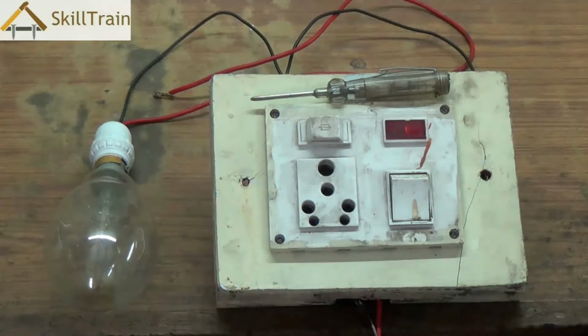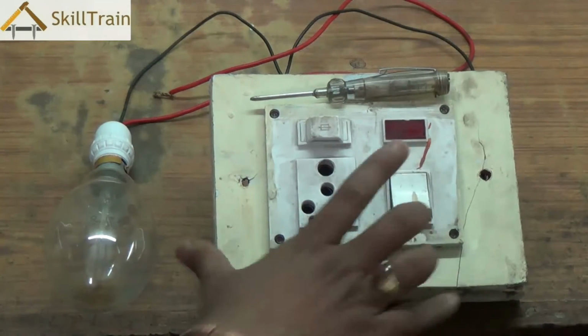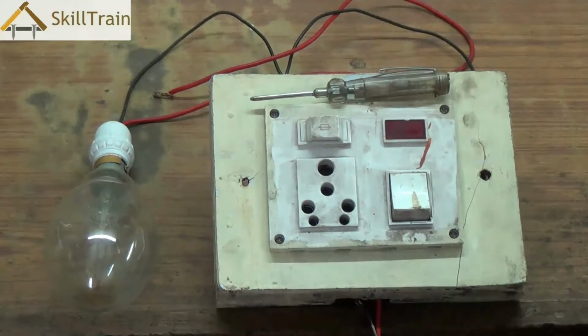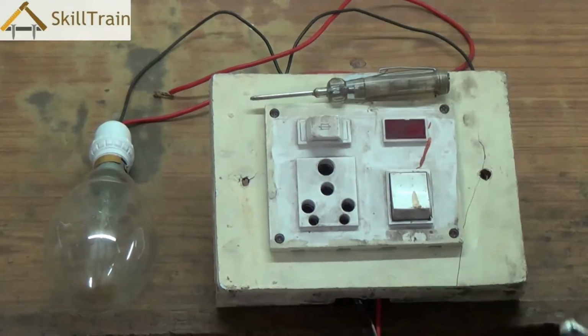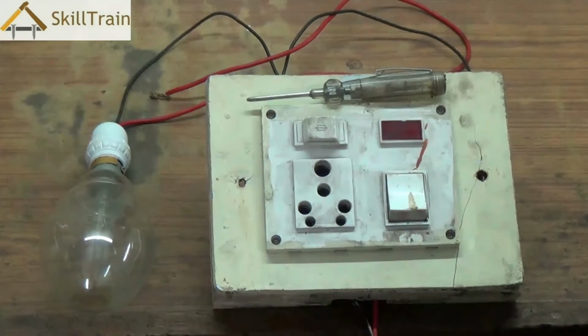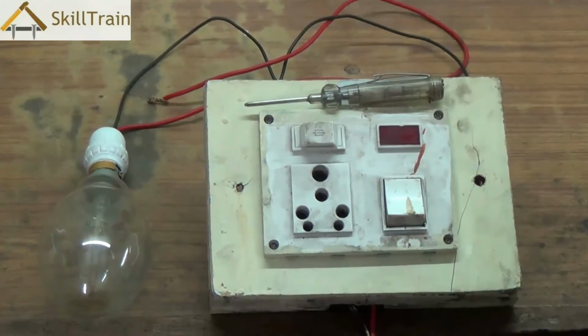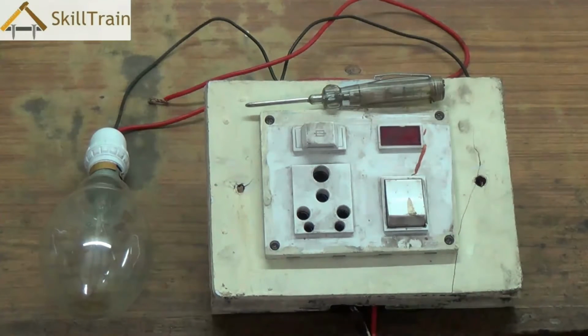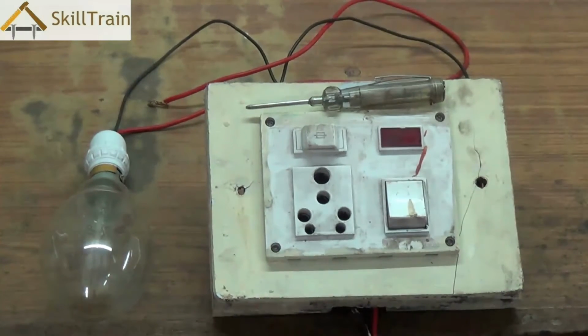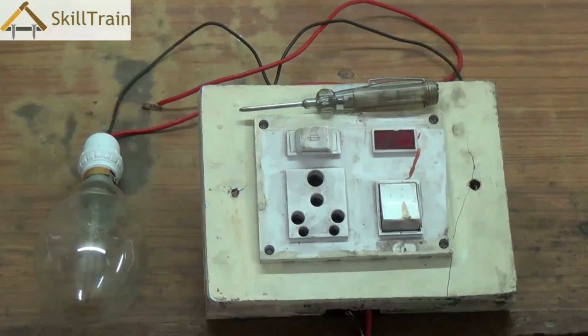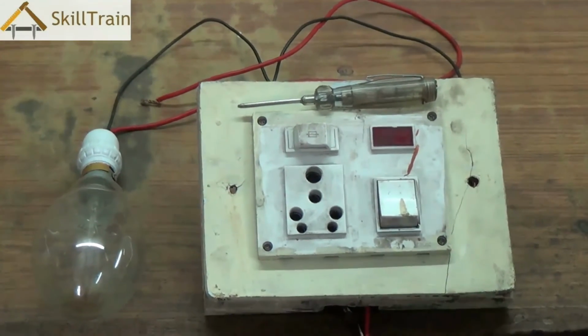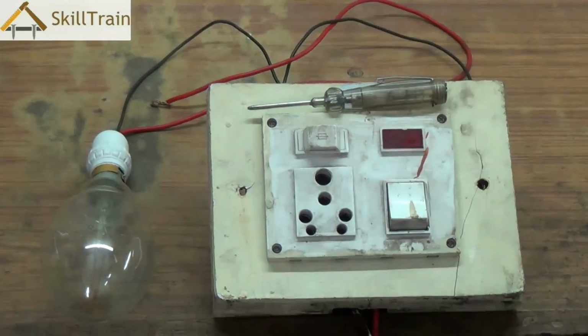As mentioned earlier, the phase can be tested using a tester, and the light glowing in the tester will tell you whether the phase is on or not. But in order to test a neutral, you will have to use an indicator lamp or a tester lamp like this. Place the 2 ends of the tester lamp, one on the phase and one on the neutral, and then check whether the neutral is intact or not. If the neutral is intact and the phase is intact, your appliances will function properly.